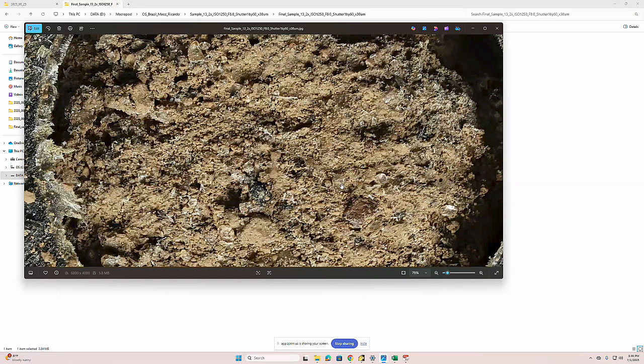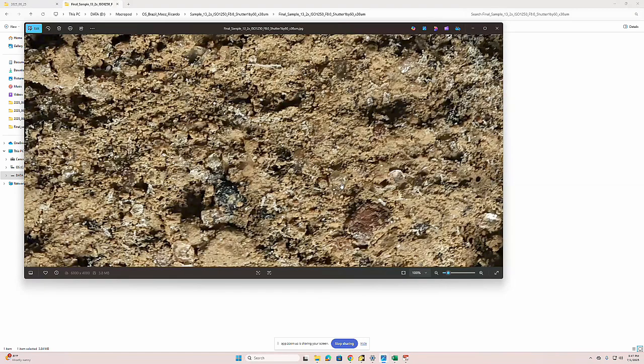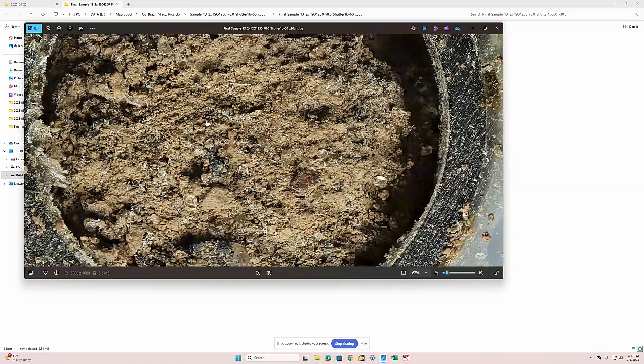So starting with lighting, because that's the first issue. That's going to be in your setup. So first thing is you definitely want to stay fixed. If you're at 2x, you want to be using 300 microns for your step size. So that's the first thing. The second is you've got the flashes on there, which is great, but if you zoom out a bit, you can see how there's significant shadows everywhere.